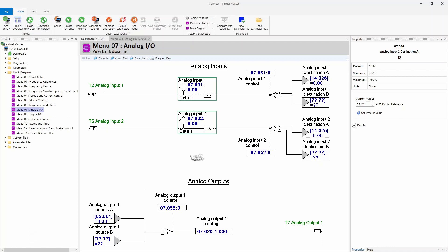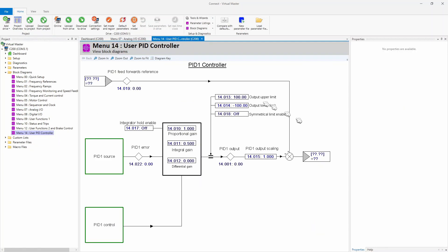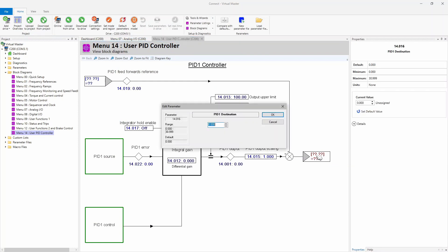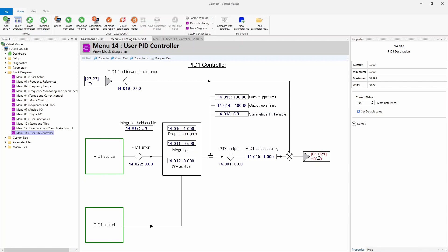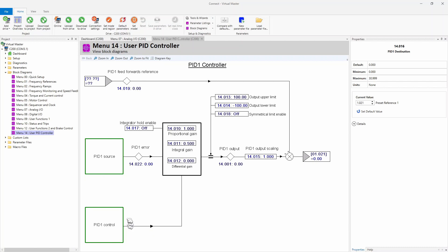The next thing we're going to do is come over here to our PID controller. We're going to map the output side of this to our preset references. Okay, that's parameter 121. As you can see, that's 01 represents menu one, and 21 is the preset for preset one. And if we come down here to the PID controller right here in this block, you will find that there is a PID enable.